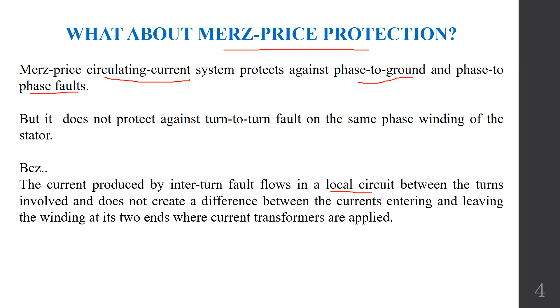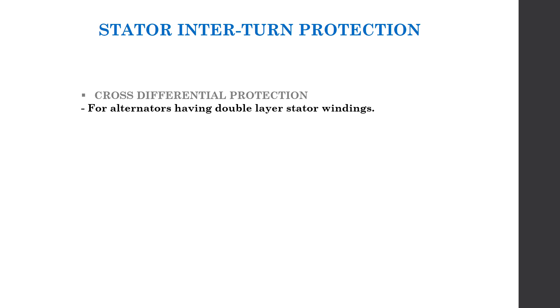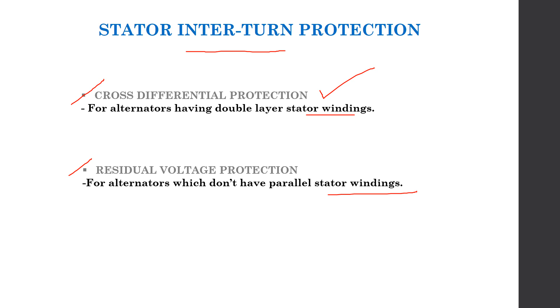The stator inter-turn protection. There are two types of stator inter-turn fault protection. One is cross differential protection and the second one is the residual voltage protection. Both the protection schemes are applied for stator inter-turn faults but for different alternators. For alternators having double layer stator windings, just in case of hydro generators, we use cross differential protection. But for the alternators which don't have parallel stator windings, we use residual voltage protection for providing the protection against inter-turn faults. We will be discussing them one by one.